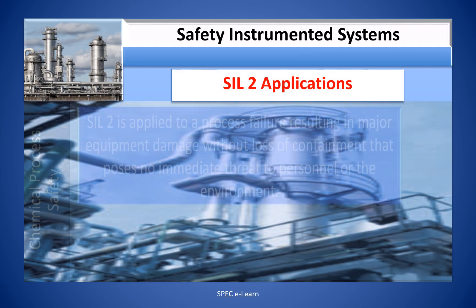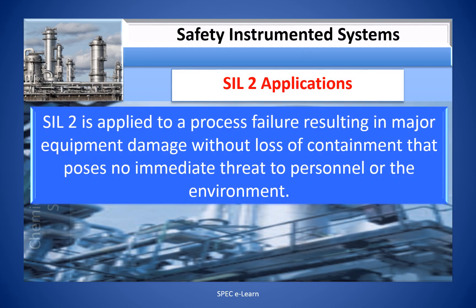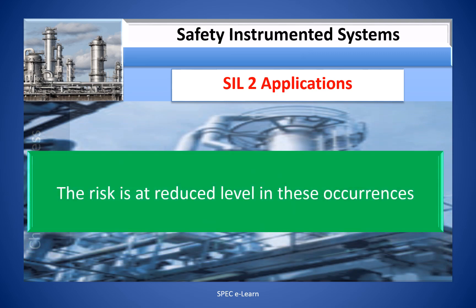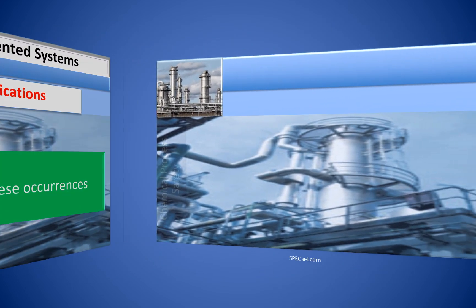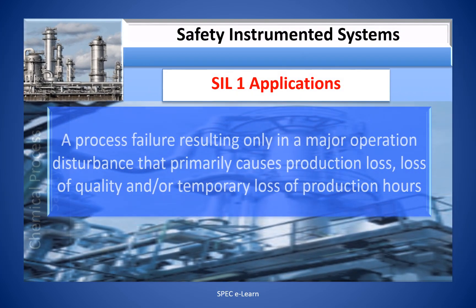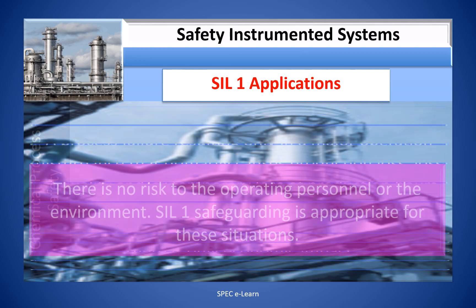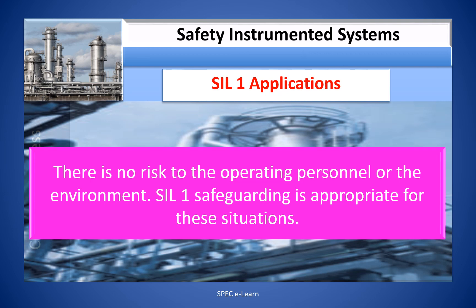SIL 2 examples: SIL 2 is applied to process failures resulting in major equipment damage without loss of containment that poses no immediate threat to personnel or the environment. The loss is primarily economic due to equipment repair or replacement and planned downtime, with the risk at a reduced level. SIL 1 examples: a process failure resulting only in a major operational disturbance that primarily causes production loss, loss of quality, or temporary loss of production hours. There is only economic impact with no risk to operating personnel or the environment. SIL 1 safeguarding is appropriate for these situations.